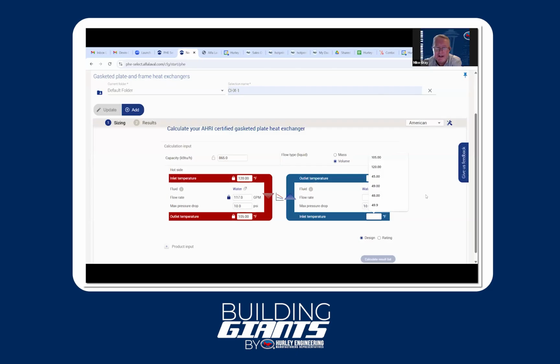It all depends on the fluids you're exchanging. Typically we see medium-high and medium-low theta plates in the designs we do with HVAC, but the more industrial side of things will see a lot more medium-high and medium or high-type chevrons, mainly because of that. It doesn't matter which plate you use, they're set up with gaps so that it's easy to clean. I'd say a high-theta plate, with its flatter curve, is probably a little easier to clean if you had to flush it.